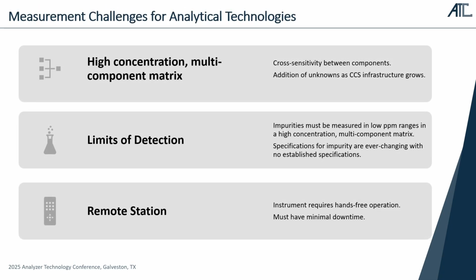That brings me to some of the measurement challenges for analytical technologies. We know this stream is going to be very high concentration. They're typically 95+% CO2, and the requirements for the impurities are usually less than 10 ppm. In some cases, they are closer to 1 ppm for each individual one. And there's also a lot of potential for additional unknowns to be introduced into the process over time. As carbon capture technology continues to grow, there's probably 30 different proprietary amines that are used right now. It's going to continue to change over time, so there's not really a common set right now.